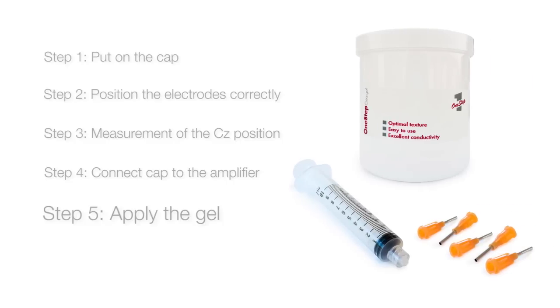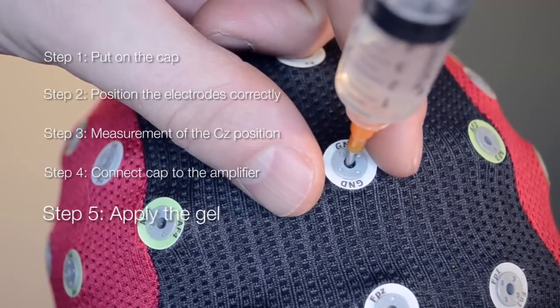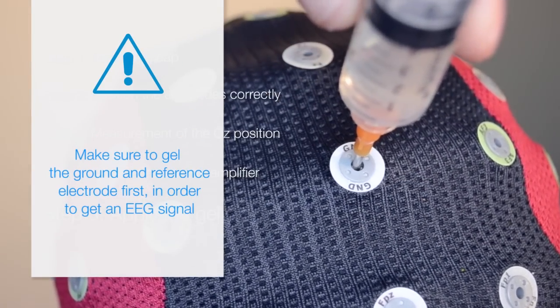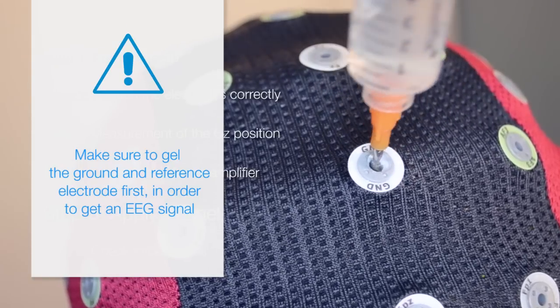Apply gel using a dedicated syringe. Blunt needles allow for easy insertion of gel through the hole at the top of each electrode. Fill the syringe with gel and inject a small amount through the hole in each electrode. Apply the gel with a circular hand movement.